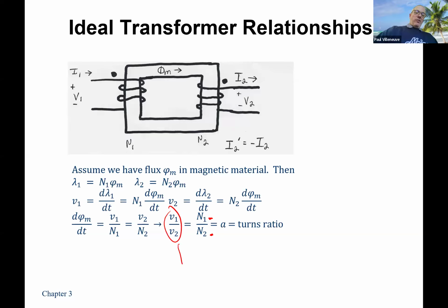In fact, it's a lot more useful to talk about turns ratio as voltages, because when I buy a transformer, and I'm told the turns ratio is 1,000, can I plug that transformer into my outlet over here? Maybe I can, maybe I can't. What if the windings were rated for like 5 millivolts and 50 millivolts? Plugging that into my outlet would burn up the transformer because the insulation couldn't handle it. So knowing the turns ratio as a voltage, which is 7,200 to 240, means I still get the turns ratio correct, I get 30, but I also know what that transformer is nominally rated for, so what voltages I can apply to it. So nobody ever talks about the turns ratio as 1,000 or 30. They always talk about it from 7,200 to 240. So every transformer you buy, even if you buy one for your senior project, it's going to be 120 to 5 volts or something like that. That's the typical way that you'll talk about it.